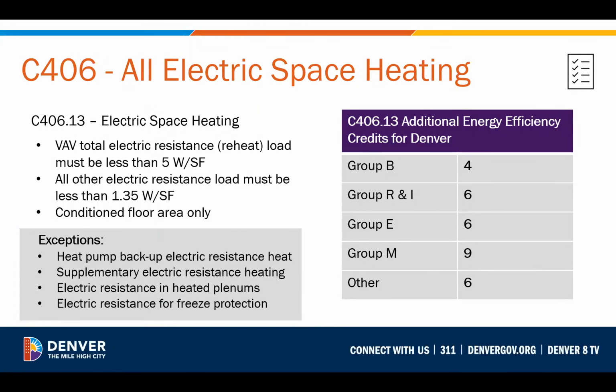So the first one being electric space heating. Again, this does not mean the building is all electric. It means that your space heating is all electric. So there are certain requirements around the amount of electric resistance you have, for VAV reheat or other electric resistance: for VAV reheat less than 5 watts per square foot, and other electric resistance being less than 1.35 watts per square foot of your conditioned floor area. Again, essentially pushing heat pumps, right? So if you're electric, heat pumps should be able to achieve this credit. Your electric resistance for your backup for your heat pump does not count towards any of that. Any freeze protection or heated plenums do not count either.